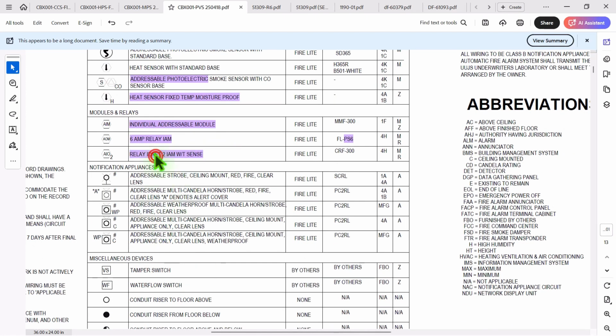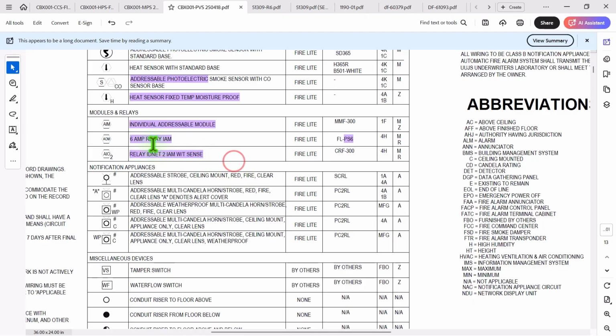Now, instead of removing this one, change it to a control module, because we'll have to wire this up in series with the relay module to connect anything high voltage. We can't connect anything high voltage directly to a fire alarm control relay, so we have to use two relays. I'll give you the wiring diagram to show you how to wire up these two relays so they know how to do it.